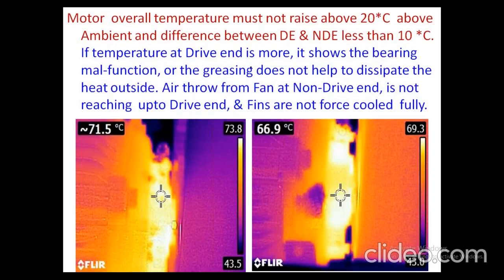A motor, as I was telling before, with an ambient of around 20 to 40 degrees, if it is around 60 degrees, it is a warm motor, it is healthy. If it is more than 80 degrees, it is not healthy. It is getting overloaded. Either the fan at the fan cowl or the fan at the non-drive end is not able to work, because the fluff has totally choked it. In a textile mill, the main curse is the fluff. It gets deposited on the motor fan cowl and automatically gets blocked. The motor non-drive end is very cool, at 20 or 30, say around 40 degrees, and the drive end goes to 90 or even 100 degrees.